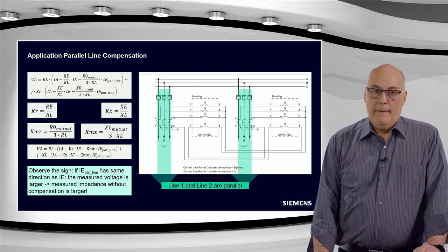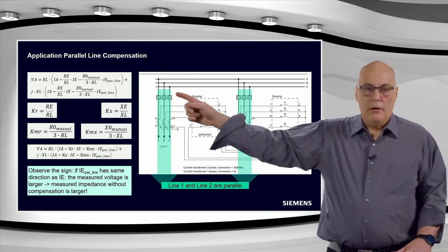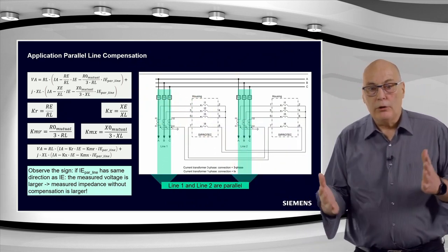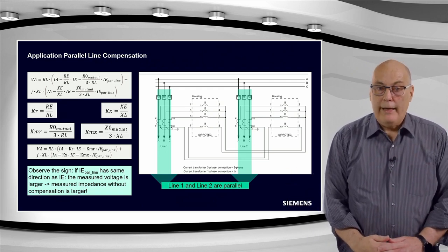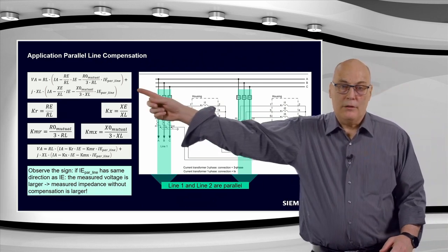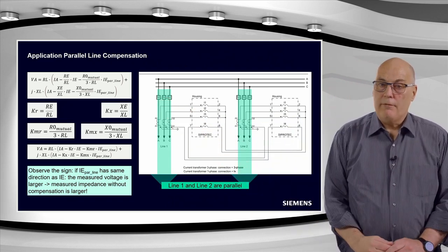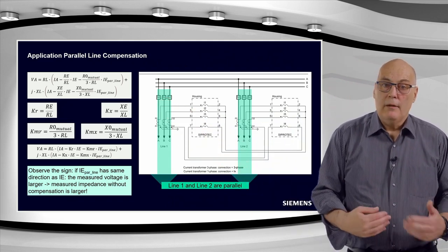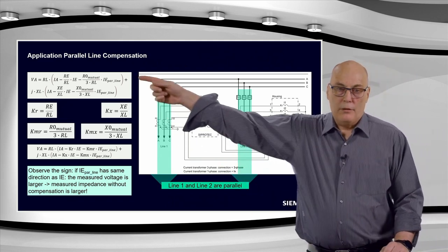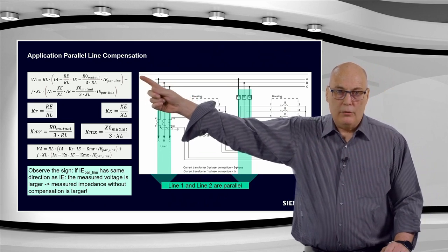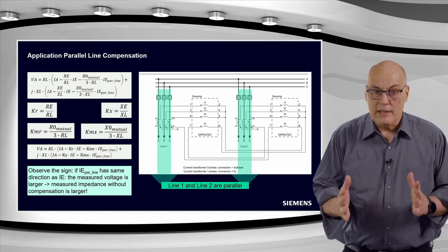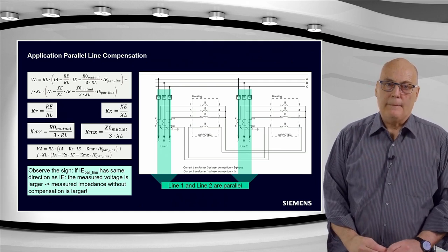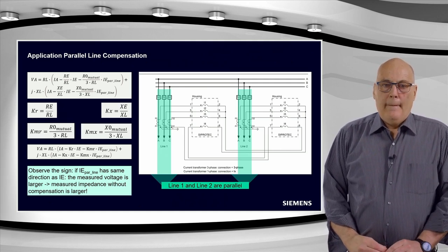At the top you can see now that's actually that previous equation, the voltage loop equation, extended now into the KR, KX method. So you can see it gets a bit longer, but it's essentially the same thing. You can split the real and imaginary components as you've shown there in the two tops. That's the same voltage loop equation there, but not written with Z's, but with R and jX as such.